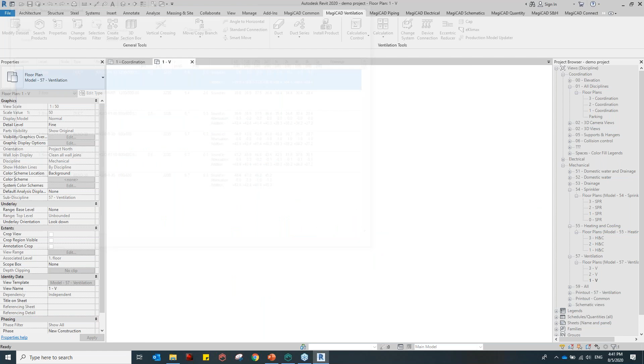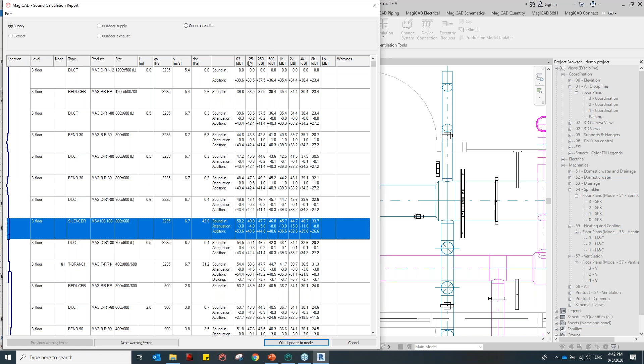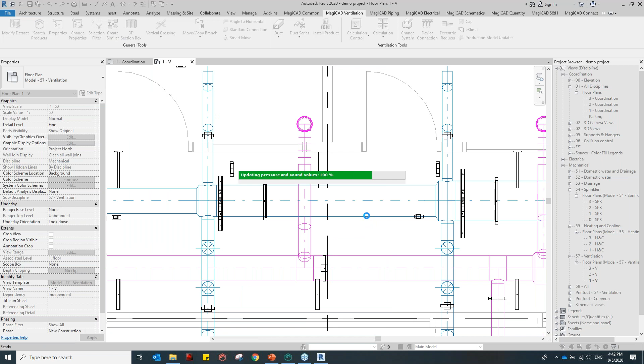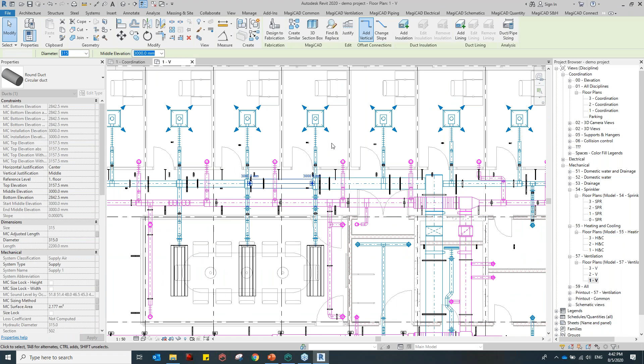I believe you're asking about the duct sound calculation, right? Yes, you can see the sound calculations here. This is based on the fan coil. If the fan coil is fixed already, you can calculate based on the fan coil. If the fan coil is not kept in the network, you can go the other way around and specify based on the fan coil input. You can put sound information of the fan coil into the product, and then carry out the sound calculations, and we'll balance the sound accordingly. Once you click update, this sound information is transferred into the ducts.